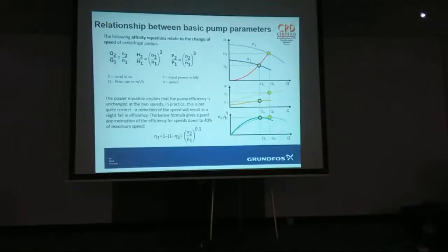A number of people, I've selected pumps from various consultants in this area, where it's a low flow, high head, and it's been in this area of the pump, which means it's in this area of the efficiency curve. 13% efficiency. Geez, it's like a spoon in a cup. But the power is down here, 250 watts. I'm not really bothered. Because if somebody's got a duty, like half a litre a second at 250 kPa on a heating system, you've got other things to worry about.